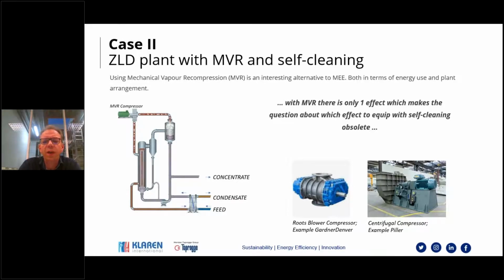Lastly, also to tell you something, a compressor, which I already mentioned, there are 2 types that one can choose. For the smaller flows, one would tend to go to a roots blower. So in fact, a quite simple machine, of course still delicate, but relatively simple, effective, although making a lot of noise. The other alternative, which you tend to use for larger capacity flows, is a centrifugal compressor. It also has a bit higher efficiency, but it can only work from the higher flows.